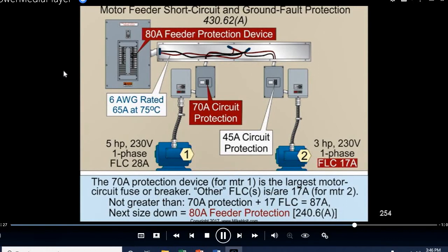So, here we go. This motor draws 28. This motor draws 17. How do you size protection for 17? Well, it's a circuit breaker, so 17 times 2.5. Let me double check my number here. 17 times 2.5 equals 43. So if it equals 43, I have to go with the next size protection device, 45. Okay, the other one is going to be 28 times 2.5. It came out to be 70. So I have a 70 amp breaker here, and then I have a 45 amp breaker there. Now this feeder protection is to be not greater than 70, which is this size right here, plus that full load current, so not to be greater than 87. Therefore, we go with an 80 amp protection device.